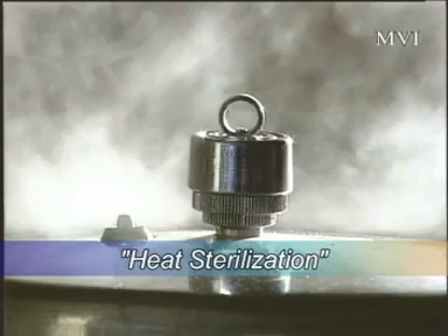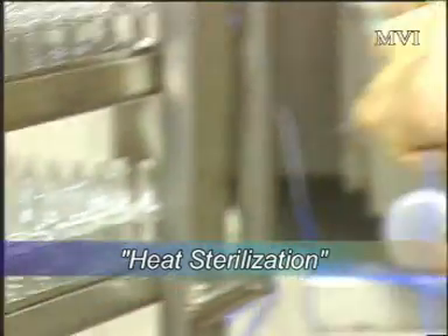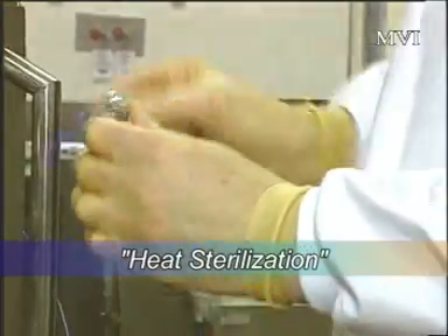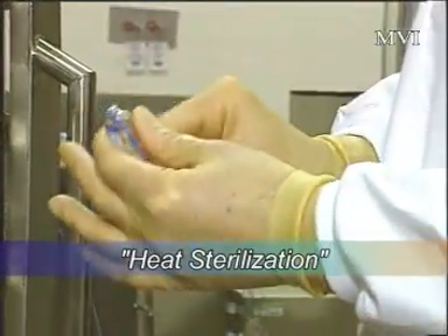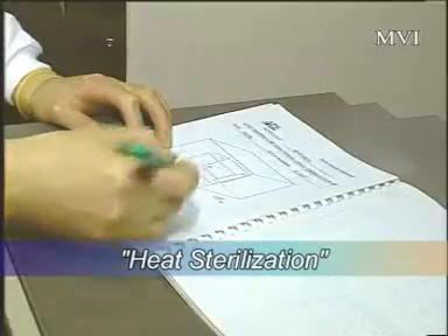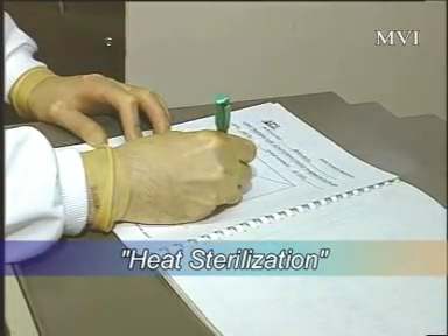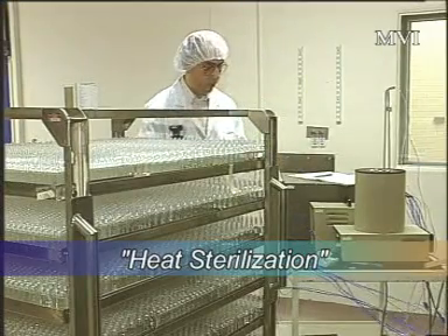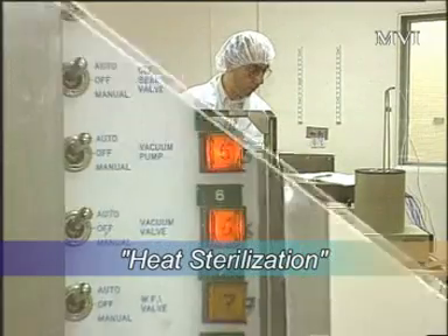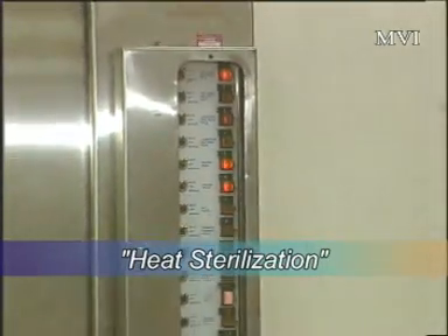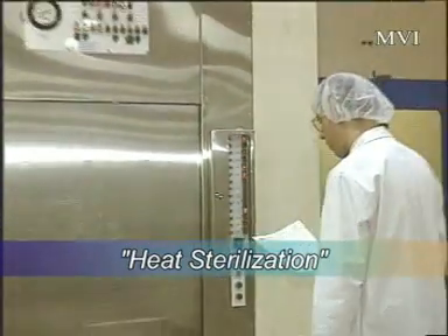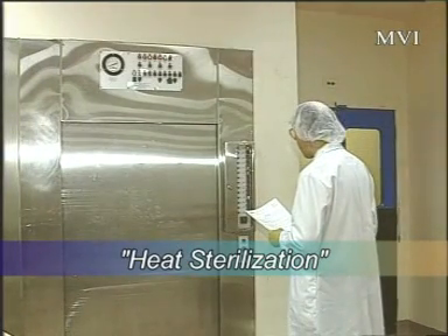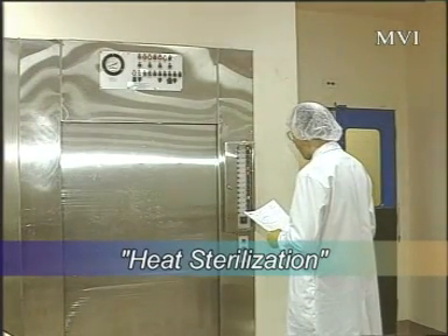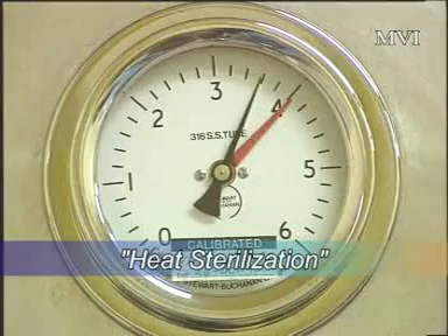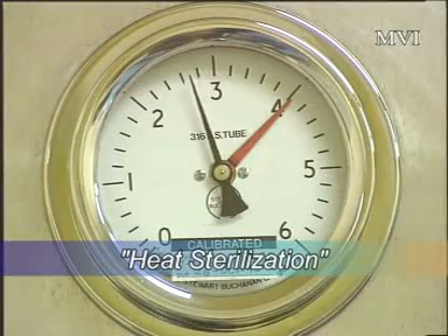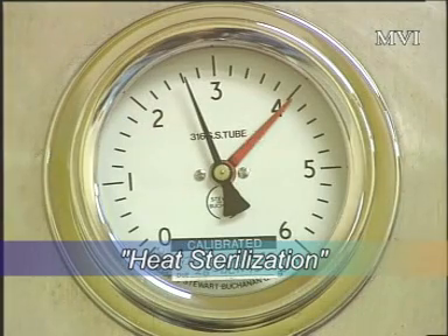They're just hotter. A product's sterilization process must be suitable for the products it will sterilize, and its efficiency in achieving the necessary sterilizing conditions for each product must be demonstrated. This efficiency must be demonstrated for every container, in every load. The validation process, procedures for operating sterilizers must be written so that they can be understood by the relevant personnel. They must be followed precisely on every occasion, and if any unforeseen changes occur, then they must be recorded and reported at once in order to determine whether the sterilization process was successful.